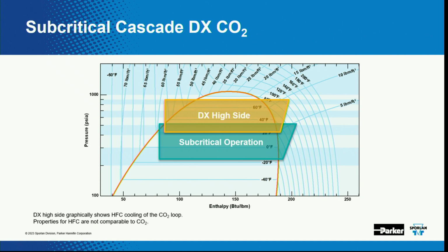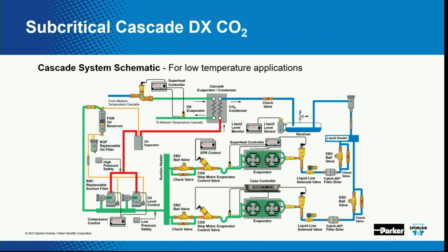But what I want to say before that is that this is not actually accurate, because this pressure enthalpy diagram is a CO2 pressure enthalpy diagram. What I've done is superimpose, let's just say, a 404 trapezoid on top of it. So that's not actually accurate, but for the purpose of diagrammatically showing you what's going on, it communicates the point. So here's the cascade system. There's still a chiller up here, a brazed plate heat exchanger. We're metering refrigerant in it, expanding refrigerant into that exchanger, and that's your HFC.